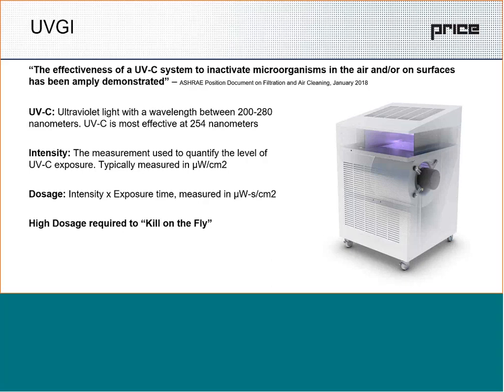A couple other key terms for UV technology is the intensity. It's the way to quantify how much energy you're getting from your UV source. It's going to be measured in microwatts per centimeter squared, typically. There are other units you can use, but that's the one you see most often in the industry. And then probably the more important one is the dosage. So it's how much intensity you're getting over a certain exposure time. And that's really what's necessary to disinfect or kill bacteria or viruses, either on a surface or in the air.